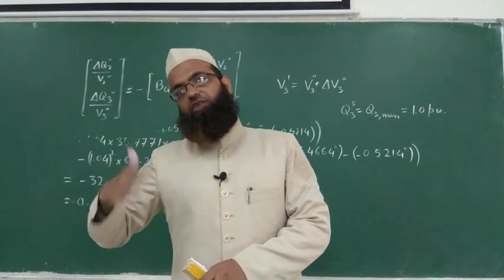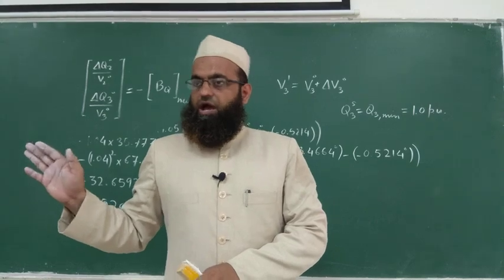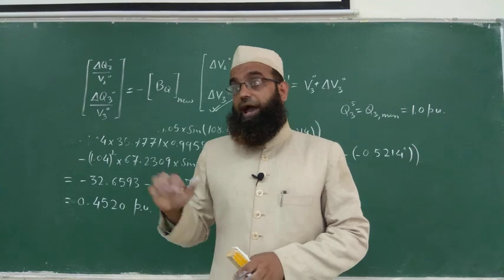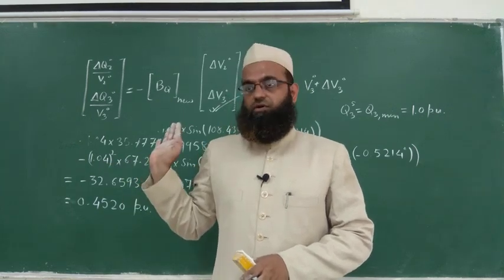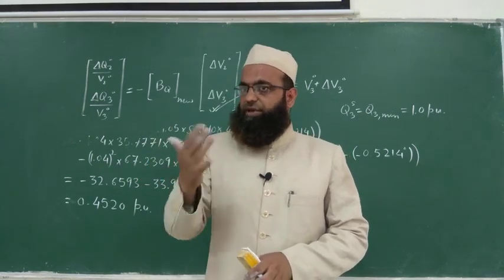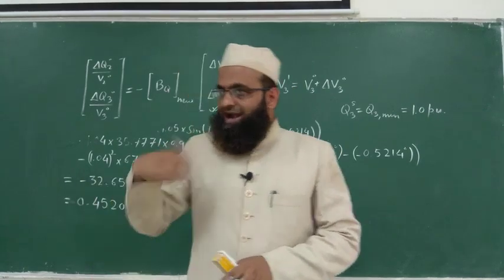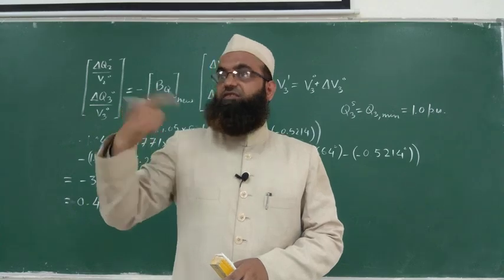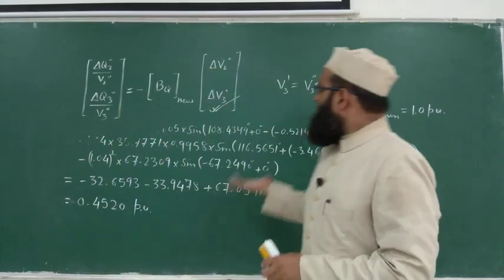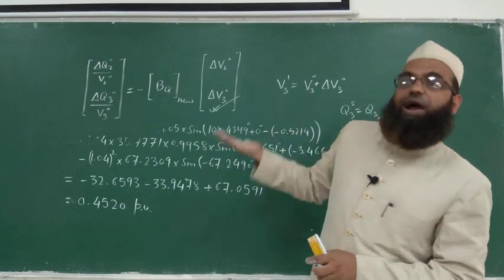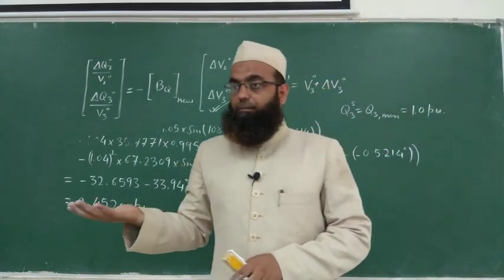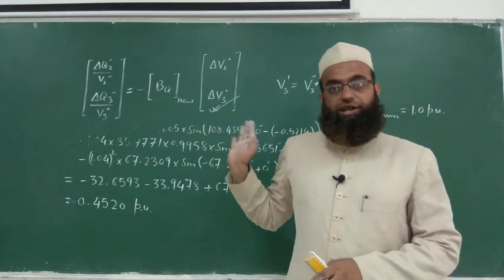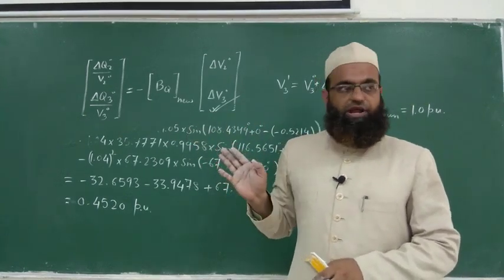So the same procedure will be repeated, and always you have to use the updated values of the variables and specified parameters, because sometimes if a PV bus is being treated as a PQ bus, then in that particular iteration the specified voltage magnitude is treated as a variable. So whatever the updated values of those specified parameters being treated as PQ bus due to limit violation will be used, the updated one in each iteration. Is it clear to you?